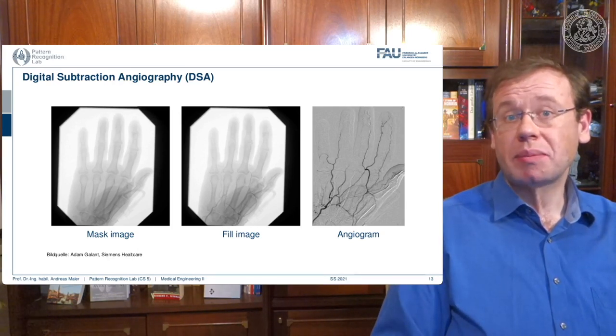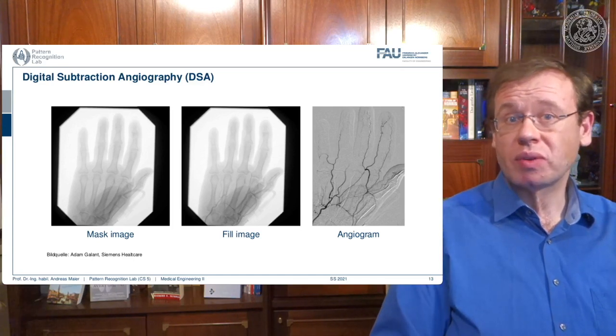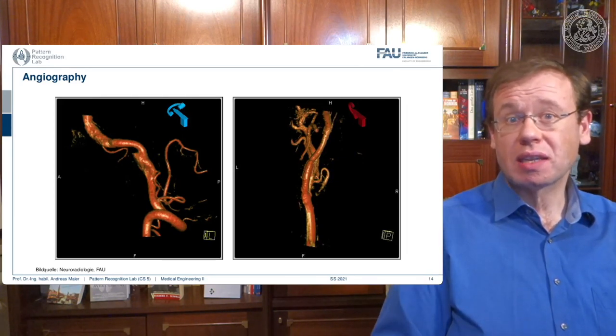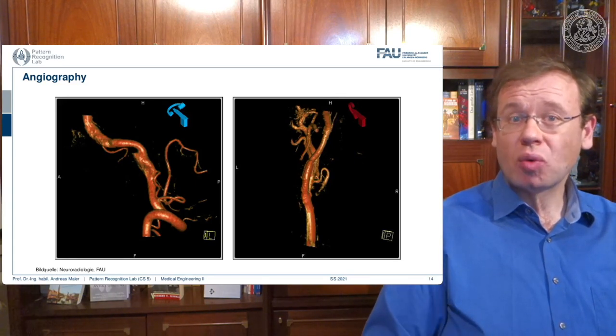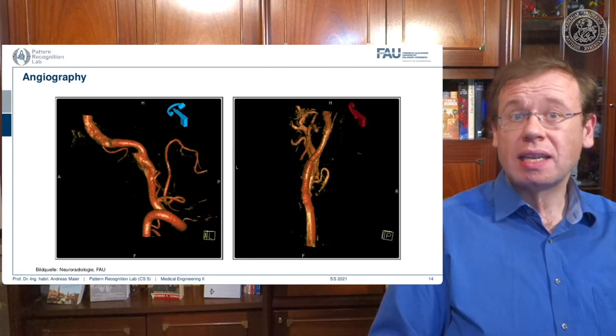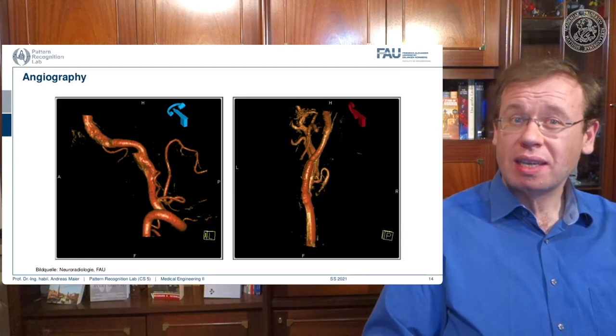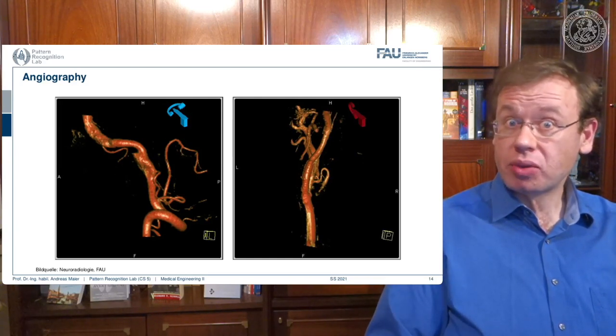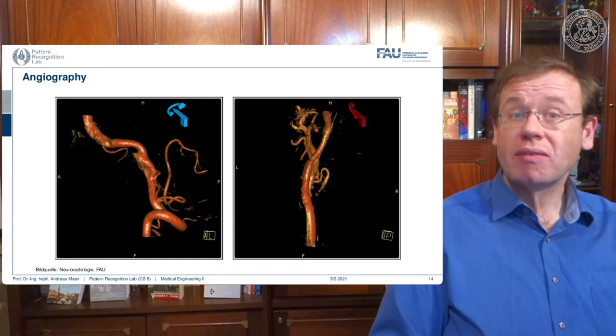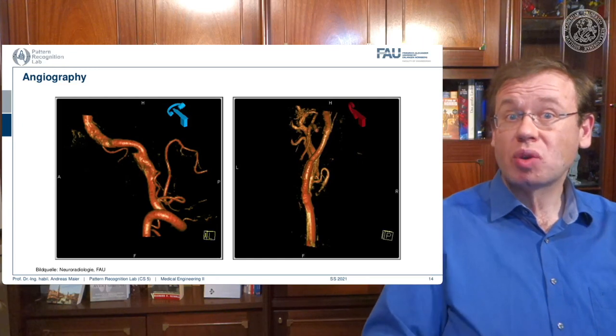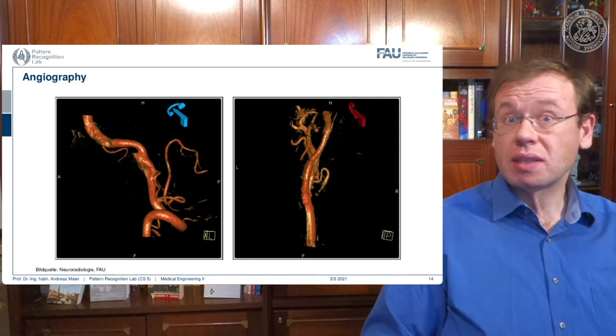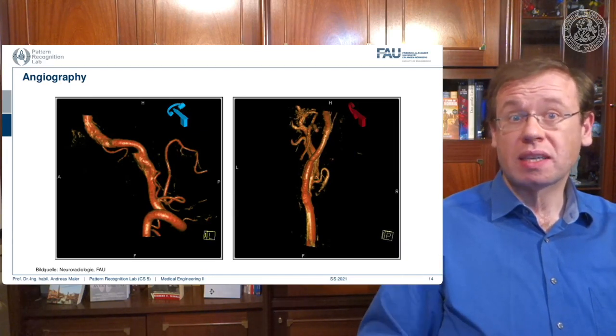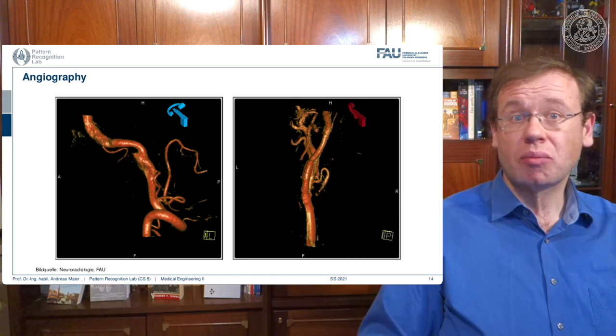In the next step, 3D imaging modalities allow you to compute the full 3D structure of the vessels. You can reconstruct the contrast agent in 3D, measure metrically in the image, and decide where to navigate next with your catheter — for example, understanding which corner you can't take with the wire. This can be done in close to real time — only a couple of seconds for a 3D image — which dramatically improves navigation.